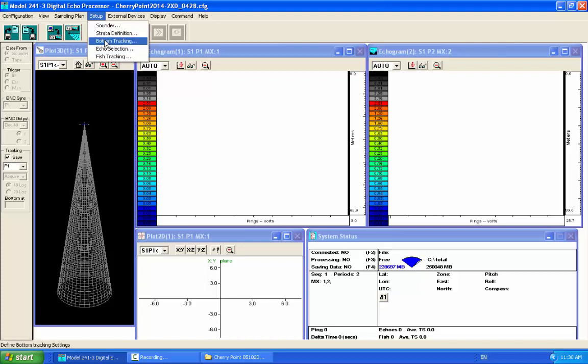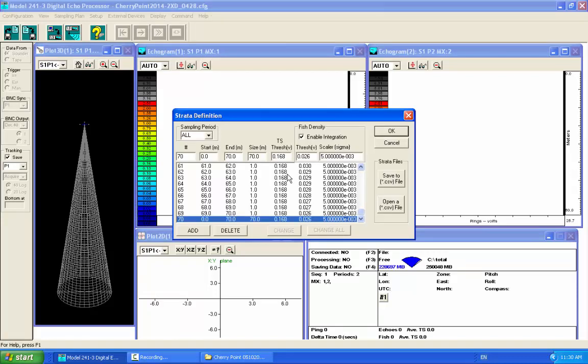The other ones I'll look at, I think we've already kind of looked at strata definition, where we basically just put in the threshold, which through that acoustic equation, or reduced form of it, is just based on our power output settings, the voltage of the smallest fish of interest that'll get logged. For target tracking studies, it wouldn't matter really whether you're collecting the integration data or not. These thresholds to the right and the scalars just apply to echo integration. And for most people, if they're just doing simple strata, you can just key in any changes, but you can port these out to Excel and change them and bring them back in also if you're doing something complicated.